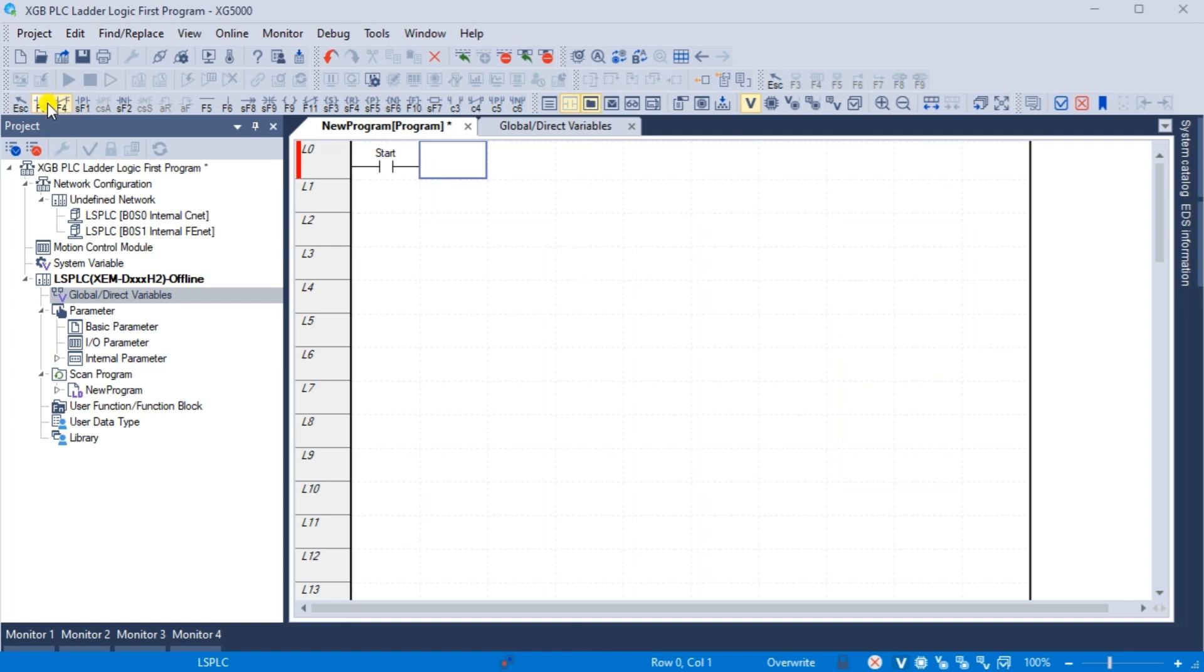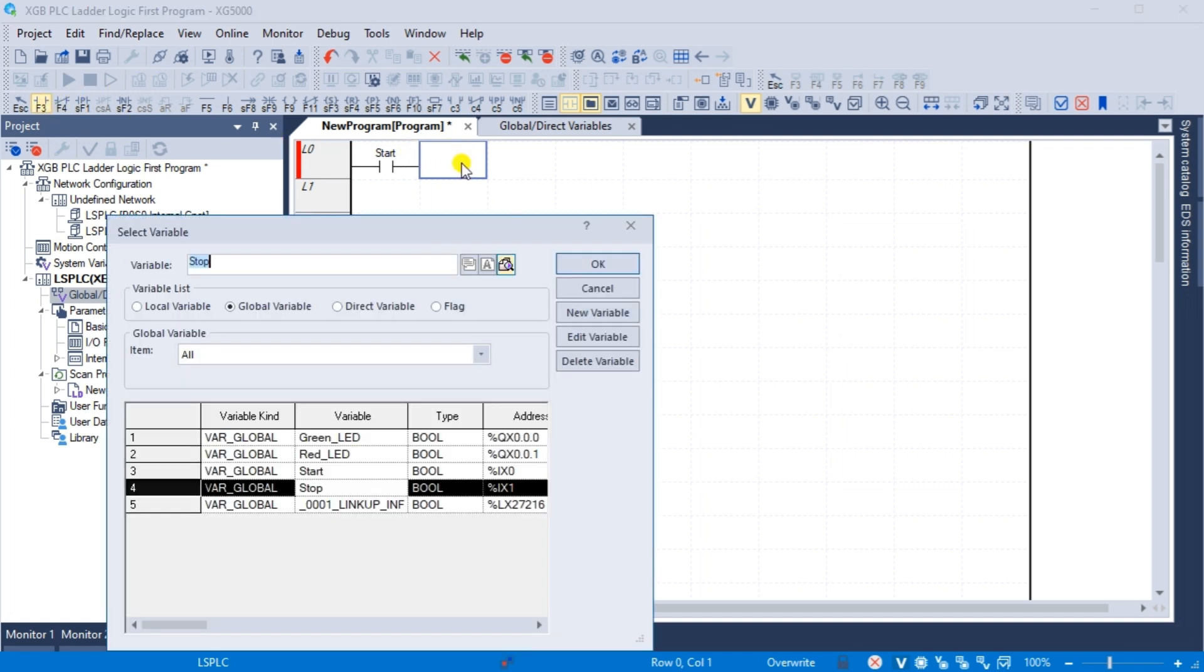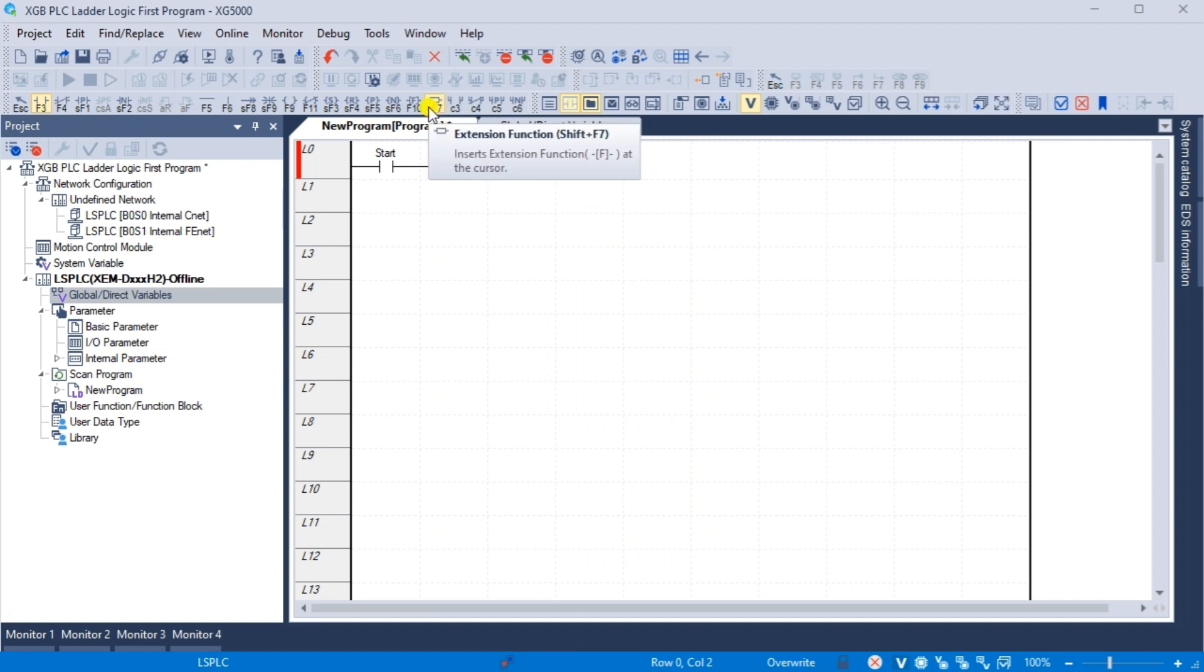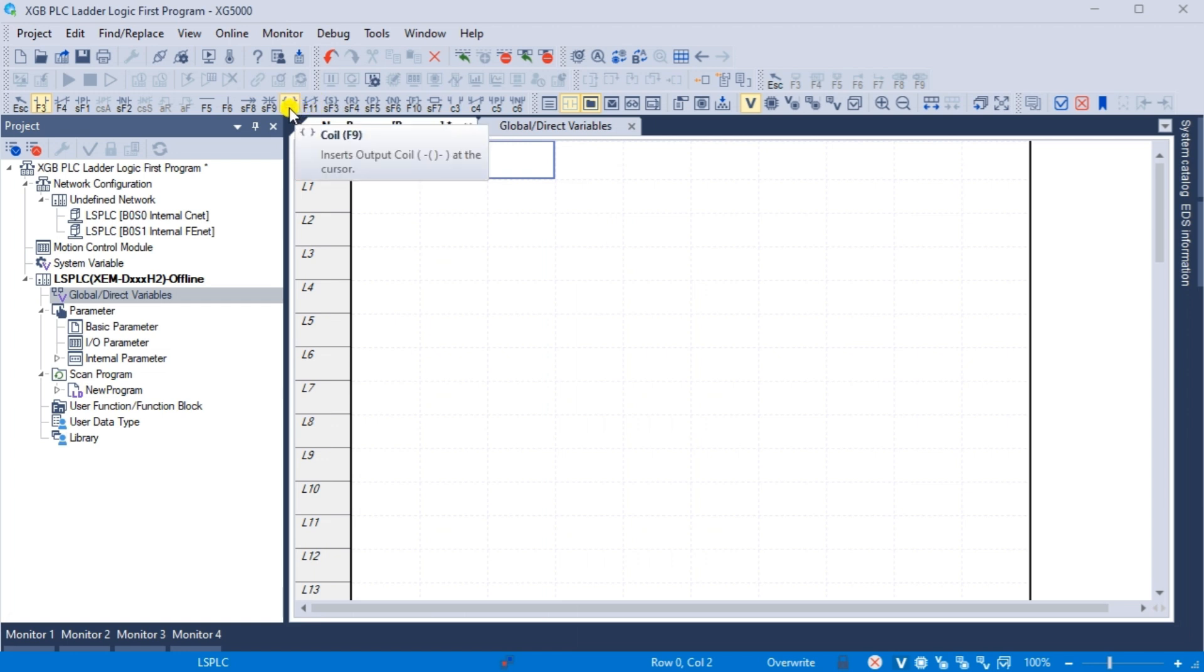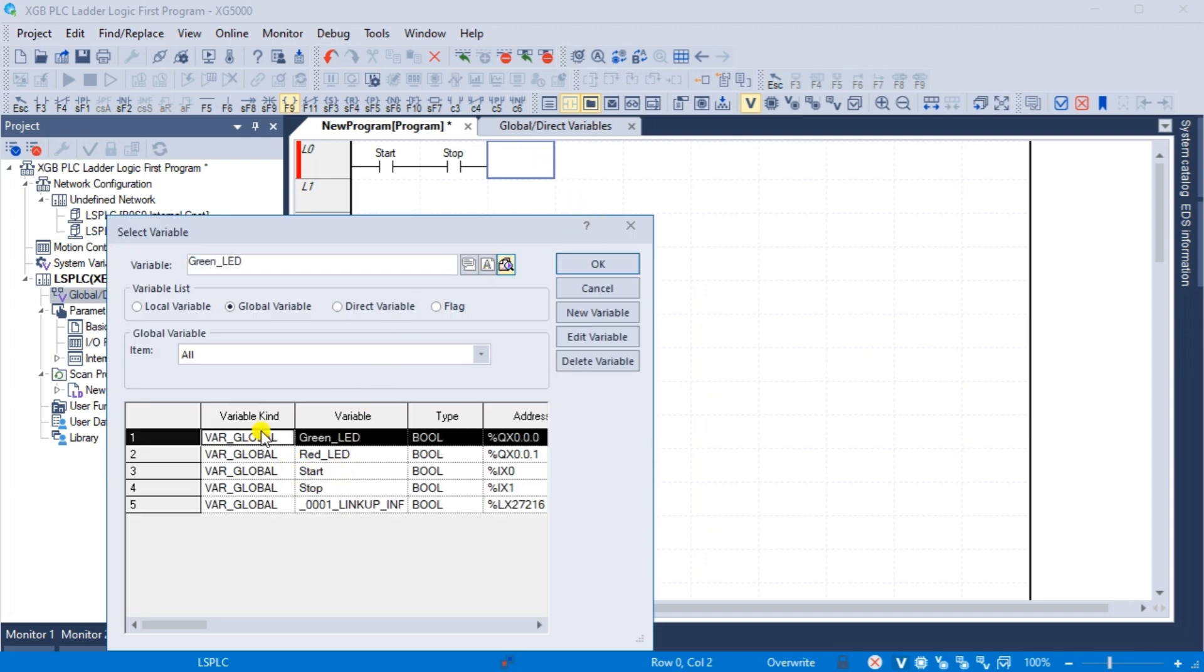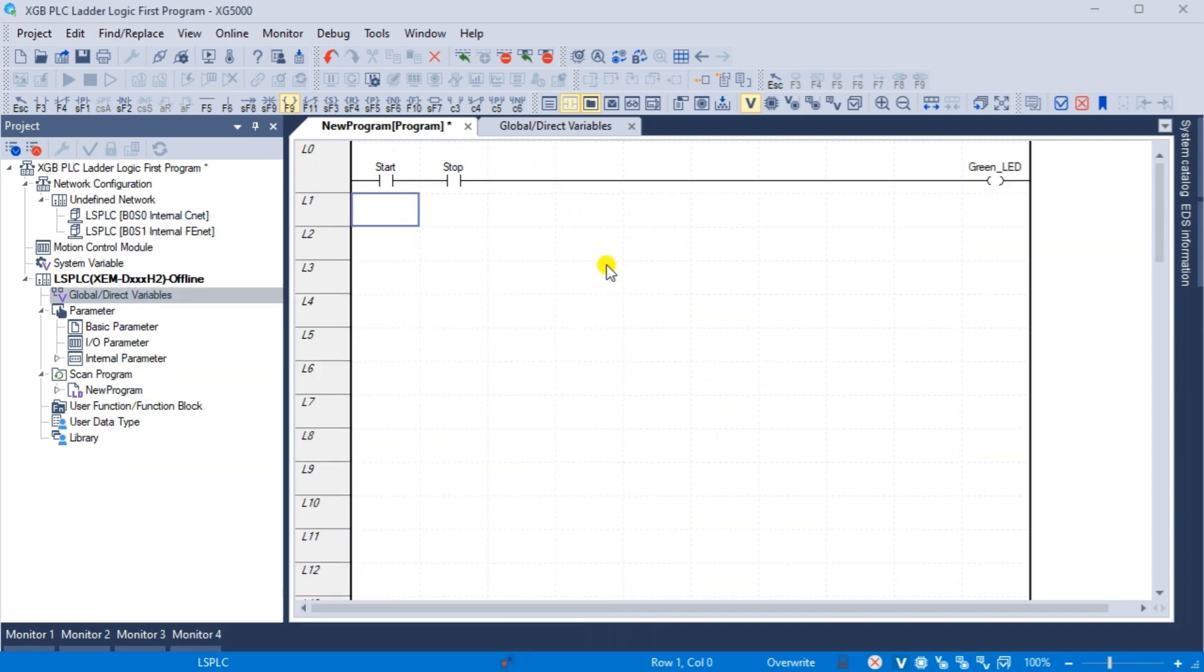Our stop input will now be put next to our start contact. Since the stop push button is wired normally closed, we will use a normally open contact. Select the output contact F9 and click on location after the stop input. Select the green LED variable and OK. This will automatically draw a line to the right hand side of the rung.